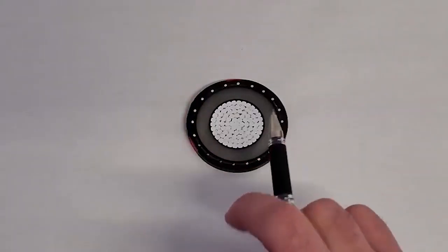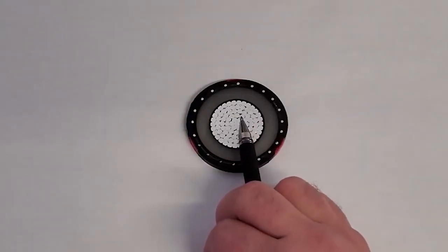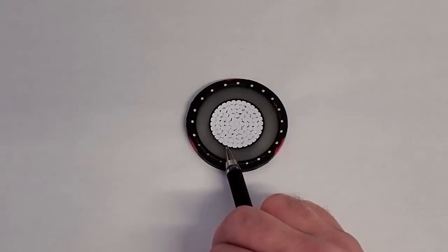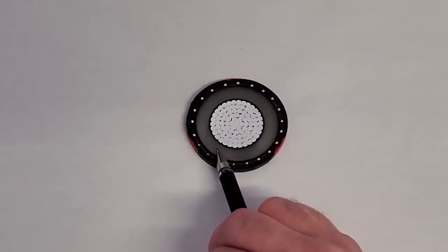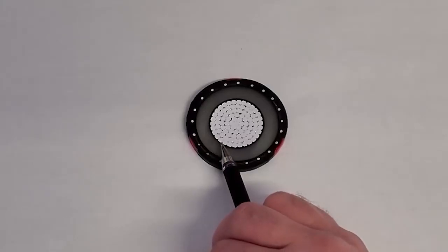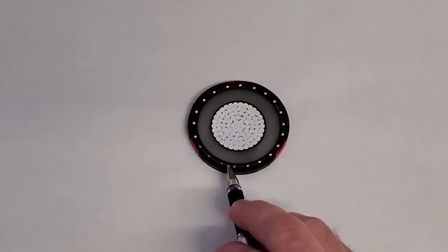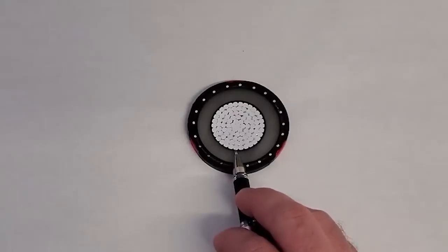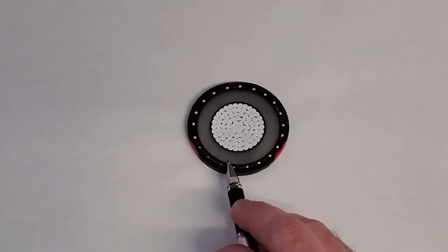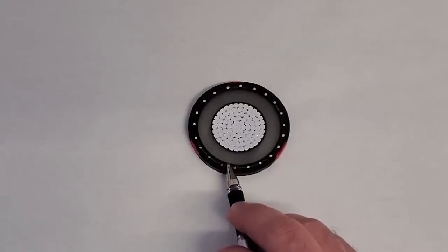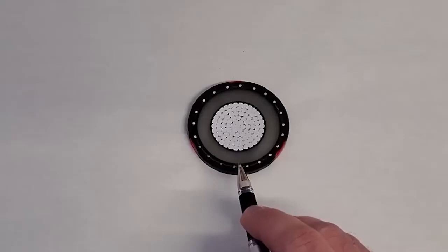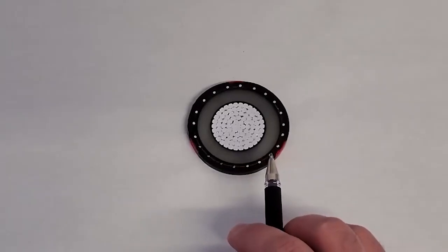And how they make this is they extrude it in a few layers at the same time under a lot of heat and a lot of pressure. The conductor goes into the extrusion machine, and it puts the conductor shield on, it puts the insulation on, and it puts the semiconductive layer on as well, which is called the insulation shield. So this one is the insulation shield, the other one is the conductor shield. So we'll talk about the insulation shield next. That's actually the same material as the conductor shield. It is a semiconductive layer. It's a polyethylene mixed with acetylene black. That's what gives it the black color, and that's what allows it to be semiconductive, because of that acetylene black conductive material impregnated into it.